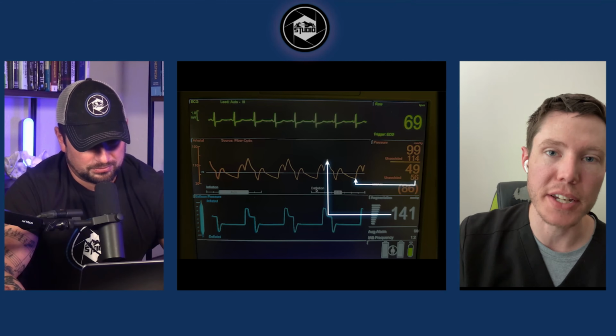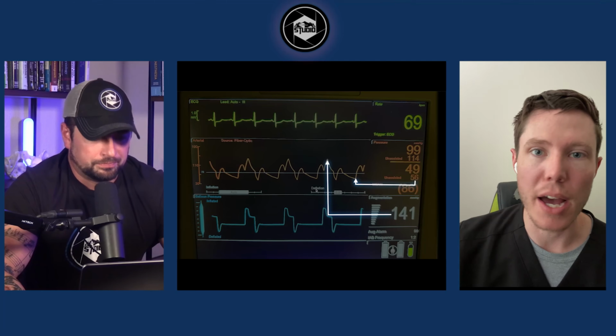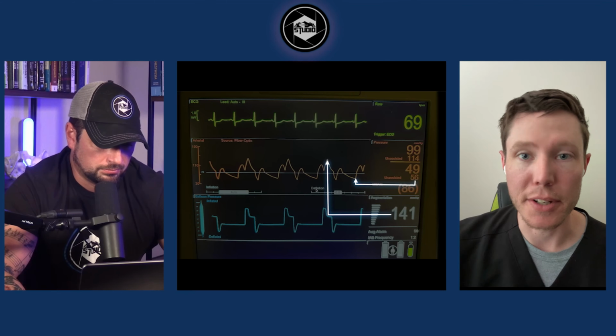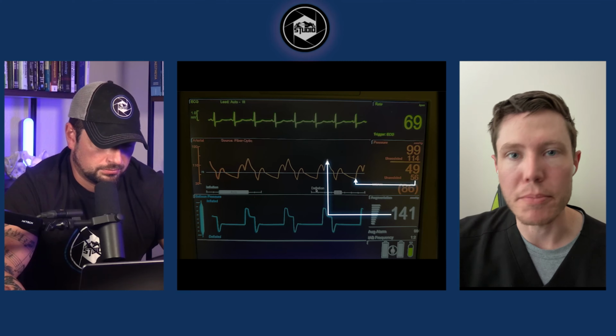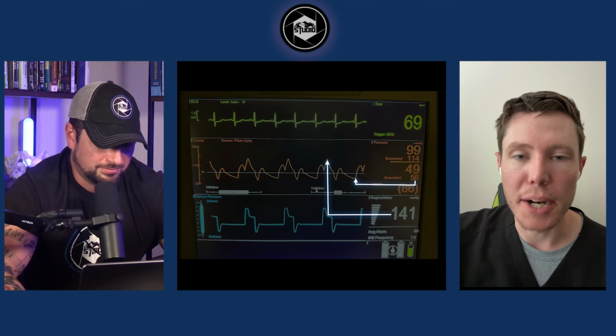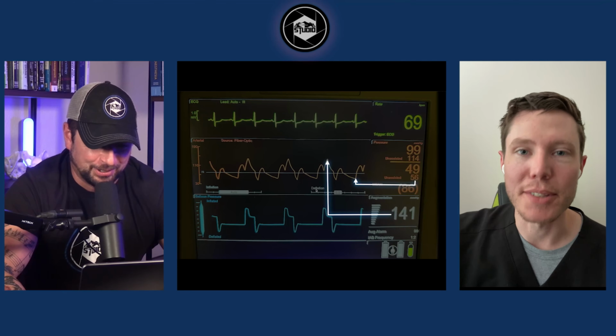I didn't mean to disparage the balloon pump's waveforms when I said it's not really truly calibrated to atmospheric air. It's zeroed and calibrated internally, and the numbers are accurate. And I'm sure whatever method they do it by is sufficient and adequate. Otherwise, obviously, we'd be having a lot more problems than we do. No, that's not what I heard. I heard you say that it was terrible. No. Yeah.